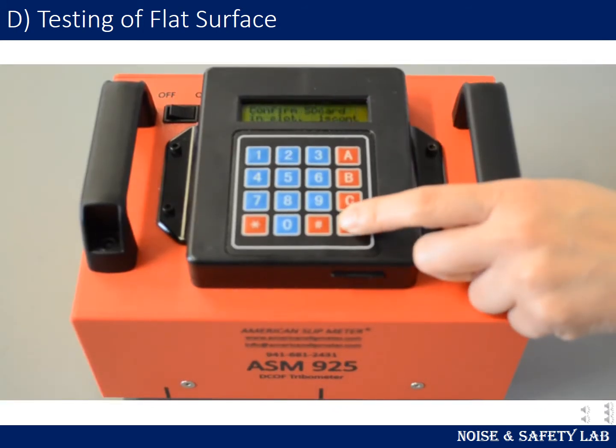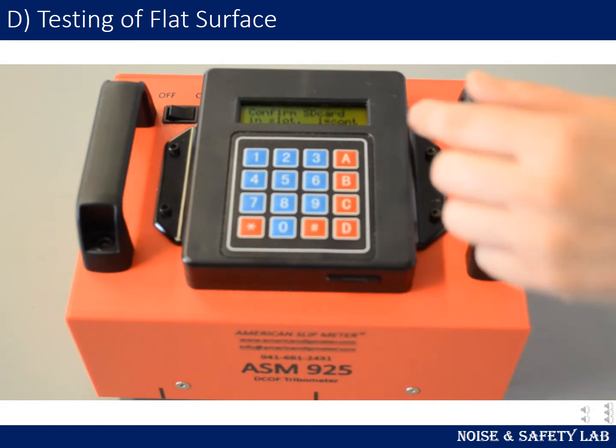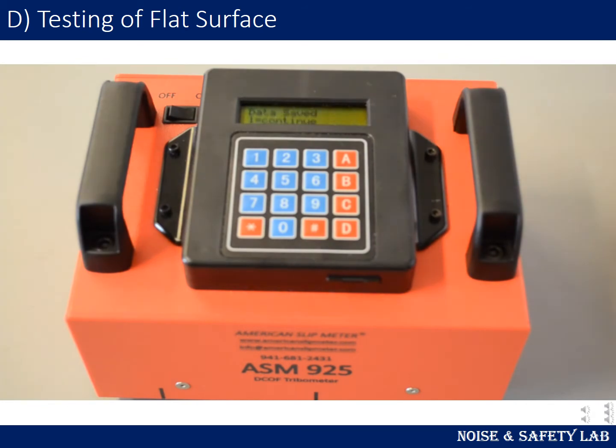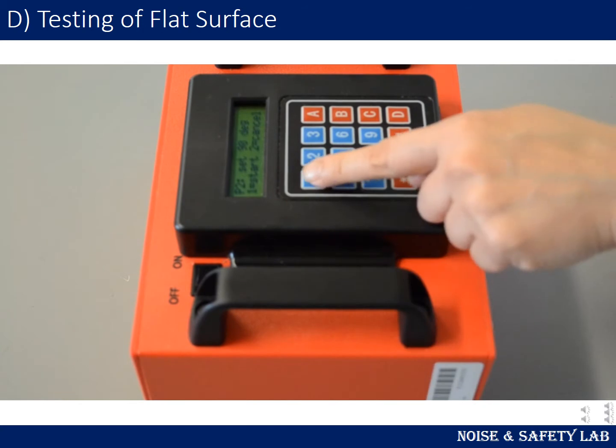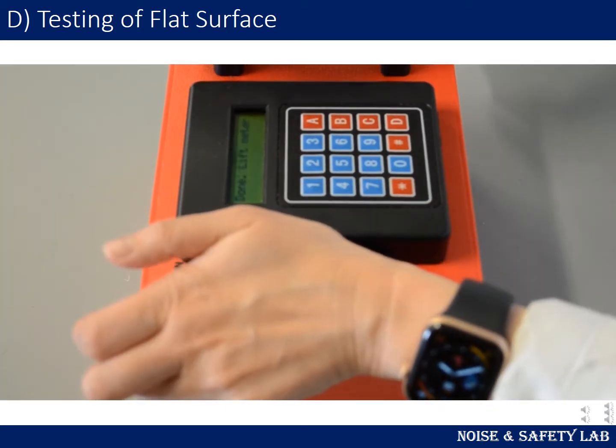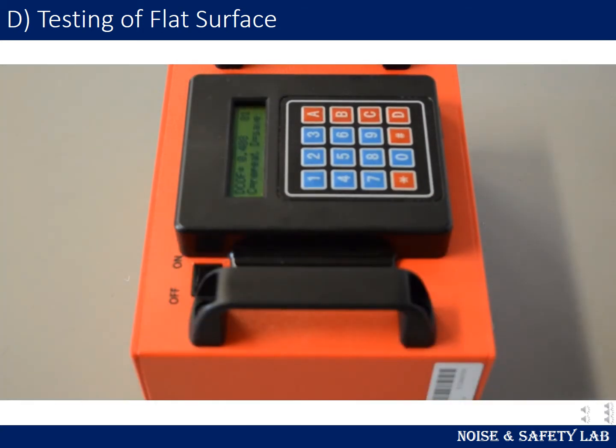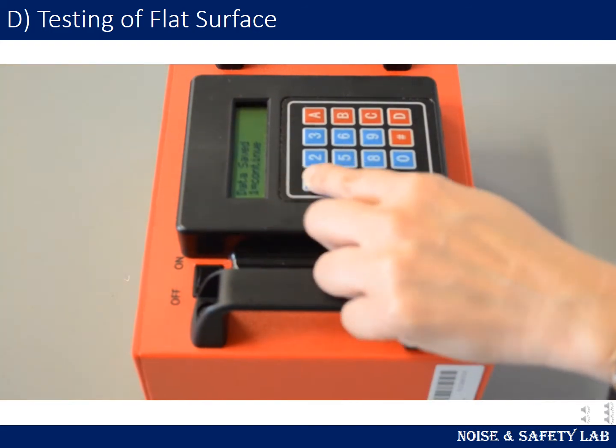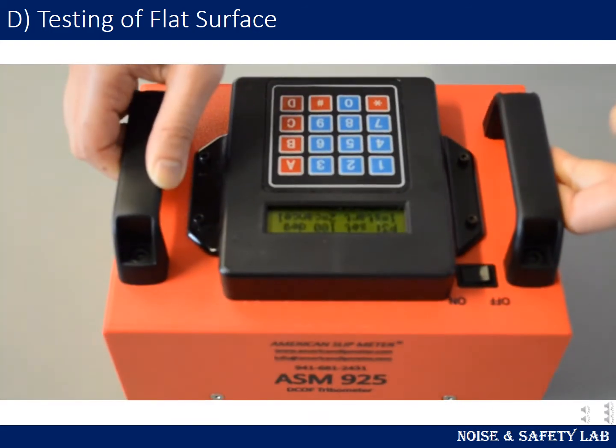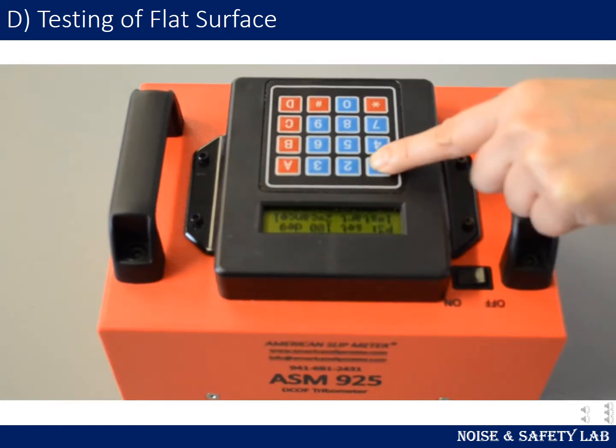Press D to save data, and then 1 to confirm SD card in slot. When the data is saved, press 1 to continue. With the meter set at 90 degrees, press 1 to start the measurement in this direction, and follow the display prompts. Repeat the measurement for 180 degree and 270 degree.